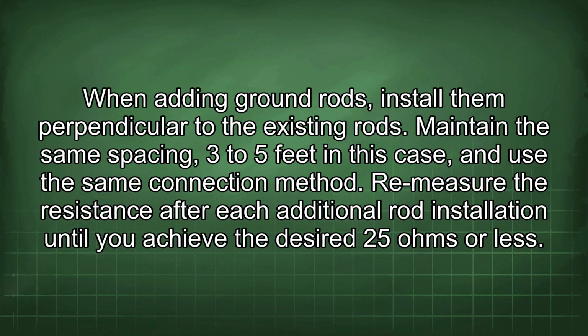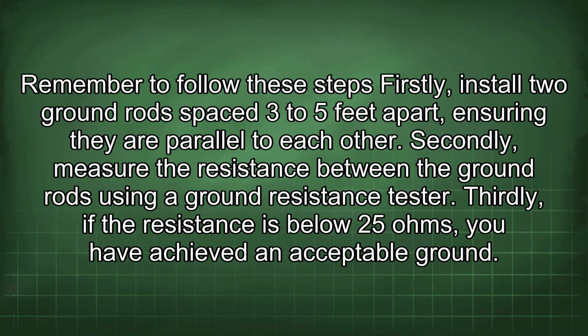When adding ground rods, install them perpendicular to the existing rods. Maintain the same spacing, 3 to 5 feet in this case, and use the same connection method. Remeasure the resistance after each additional rod installation until you achieve the desired 25 ohms or less. Remember to follow these steps.